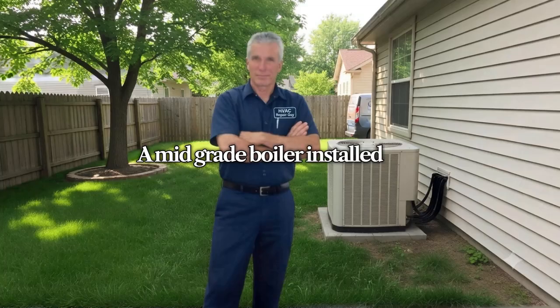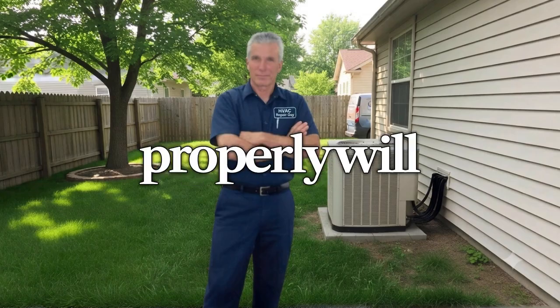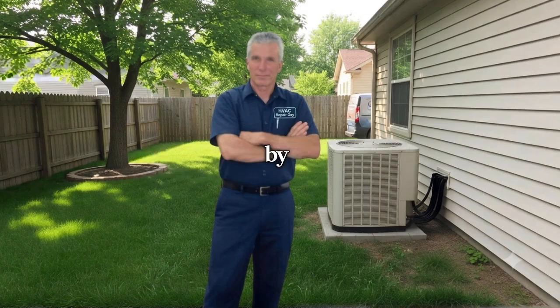Here is what the brochures won't tell you. The brand name on the jacket matters far less than the quality of the installation. A mid-grade boiler installed by a meticulous technician who sizes the piping correctly and sets up combustion properly will outlast a premium unit slapped in by someone cutting corners. Oil boilers require an annual cleaning, a new nozzle, and a proper draft check every single year.